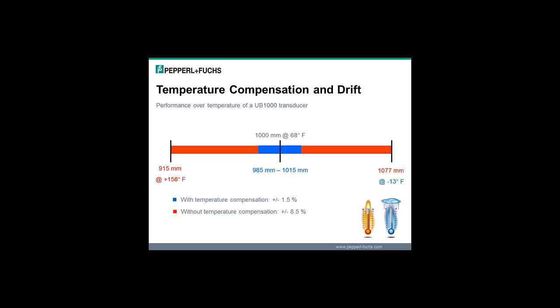You can also see here that as the temperature drops, the speed of sound slows down. So at minus 13 Fahrenheit on an uncompensated sensor, since the speed of sound slows down, the sensor thinks the target might be further away. The deviance on an uncompensated sensor might be up to plus or minus 8.5% from the 1,000 millimeters. If the temperature is minus 13, it could conceivably think that the target is 1,077 millimeters away. If the environment is extremely hot, like 158 Fahrenheit, the speed of sound goes quicker, so the sensor thinks the target might be closer. So in that instance, with the target 1,000 millimeters away, the sensor may think it's really 915 millimeters. But keep in mind, this is extremely worst case; not too many areas go down to minus 13 Fahrenheit and up to 158 Fahrenheit. And also keep in mind that most of our sensors are temperature compensated, so we're in that smaller window and not the wider window.